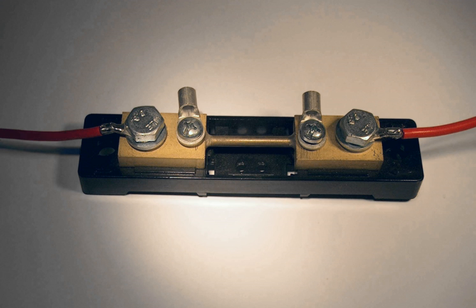Shunts are rated by maximum current and voltage drop at that current. For example, a 500A, 75 millivolts shunt would have a resistance of 150 microohms, a maximum allowable current of 500 amps and at that current the voltage drop would be 75 millivolts.